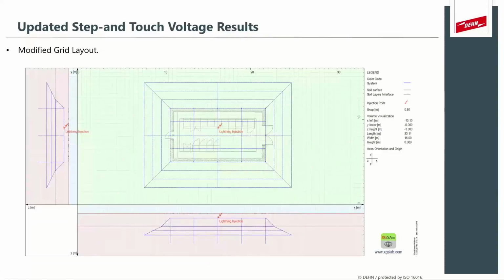If we look at our modified grid, this is what it looks like. We have the meshes put back to ensure we get an equipotential plane as much as possible. Then we apply the rings at different depths, as you can see. This at the bottom is the side view of the grid from this way, and this is the side view from this way. So you can see that we apply these rings around the grid at different depths, and we start controlling the ground potential rise curve and the steepness of the curve from the top all the way down to a safe distance away from the building as well.